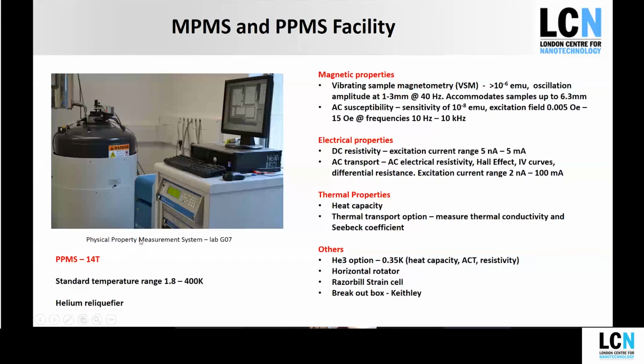And the last instrument is the PPMS, the physical property measurement system. Again, the standard temperature range is 1.8 to 400 Kelvin. This has a helium reliquefier, so it's cheaper to run than the MPMS. It has a 14 Tesla magnet, and we can do many options on here. We have a VSM, which has lower sensitivity than the SQUID, but the measurement is a lot faster, as you're doing it at 40 hertz.